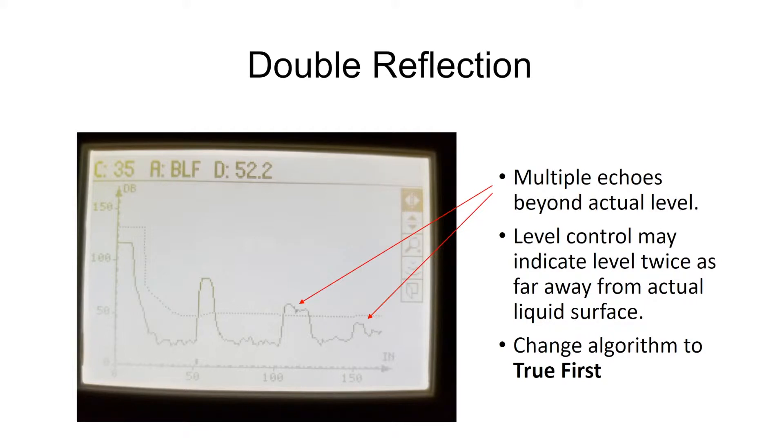In this example, we show a phenomenon called double reflection. The way ultrasonics work is the sensor creates noise, the noise goes down, bounces off the level, comes back up, we measure time of flight. In a lot of applications, if you have a flat roof or even a parabolic or curved roof, we can get a double reflection, and if everything aligns right, the double or second or third reflection can be stronger than the first reflection, and the level control picks that as our level.